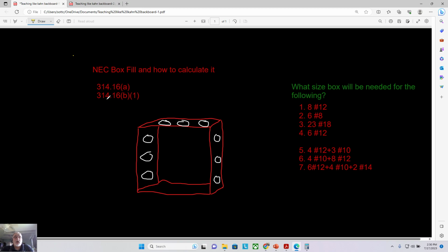A lot of the stuff that you guys have learned, very rarely do you run into it unless you're in specific conditions. One of the things that you will need to know and be able to run in your head is how many wires you can get into a box, the box fill. That's the low hanging fruit that the inspectors will come looking for to be able to give you a red tag, to make you change it. Again, this particular exercise is a junction box in a wall that could have multiple different conduits coming into it.